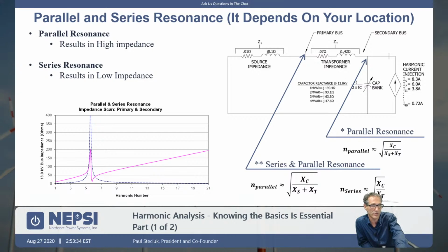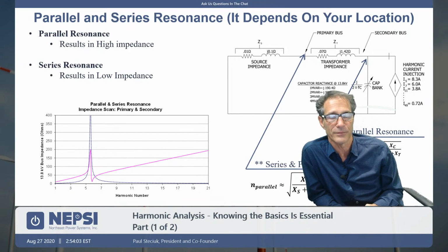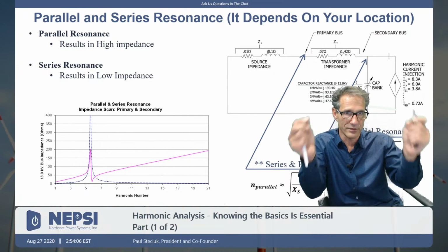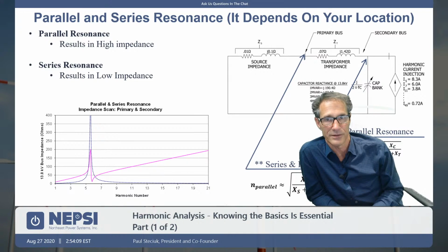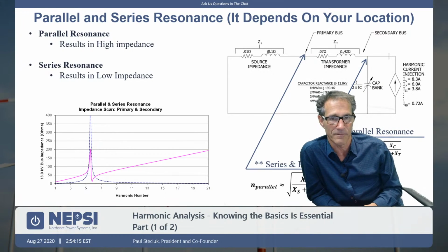Most of the harmonic analysis programs are doing a pi model or a long transmission line model, and they're capturing the capacitance of that transmission line. Does it make sense to capture that? A sensitivity analysis is what I would do there. I would look at the two impedance curves, one with it modeled, one with it not modeled, and make that determination. With that being said, we had a tech talk week before last with BBA, and Hydro-Quebec does an impedance locus. They're modeling a range of frequencies and capturing more of the possibilities of impedance changes on the transmission level.